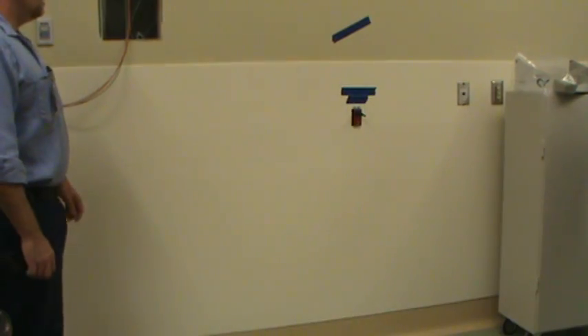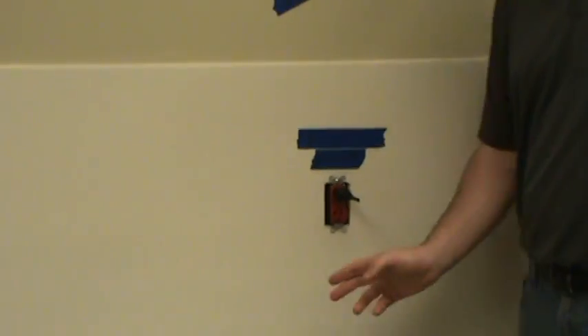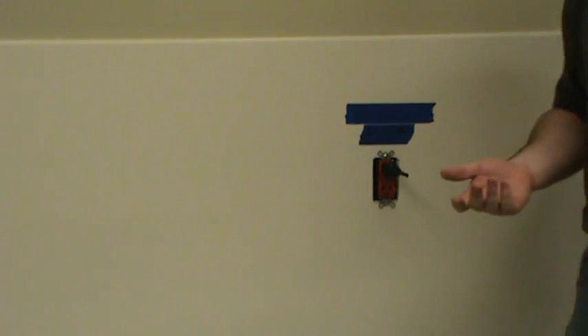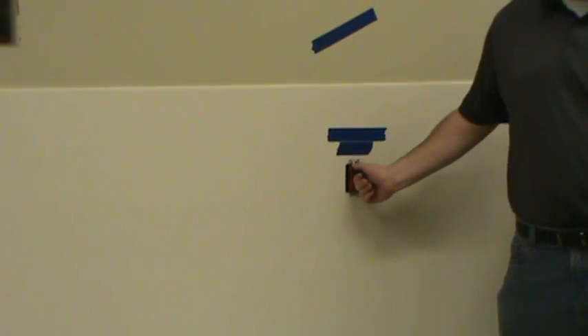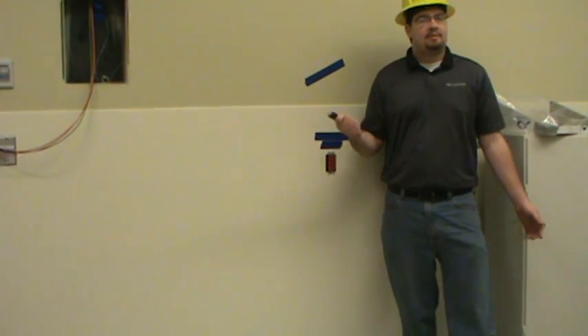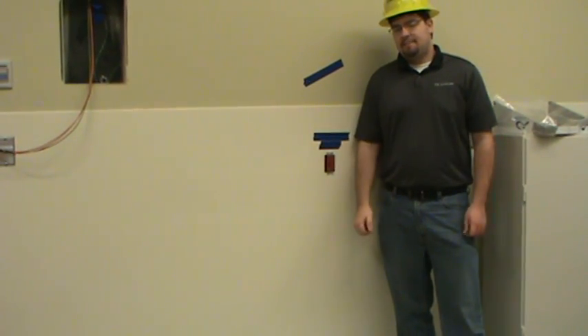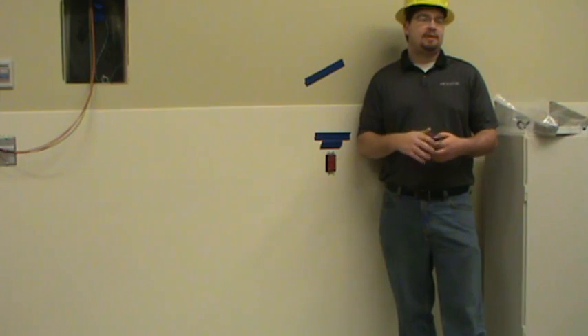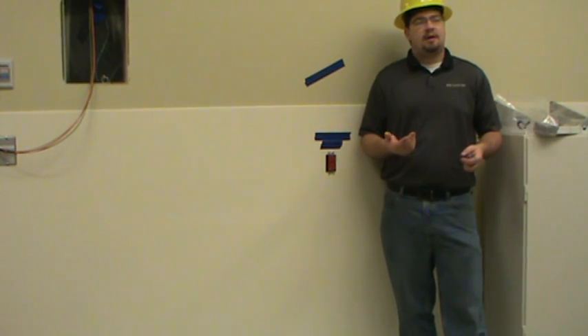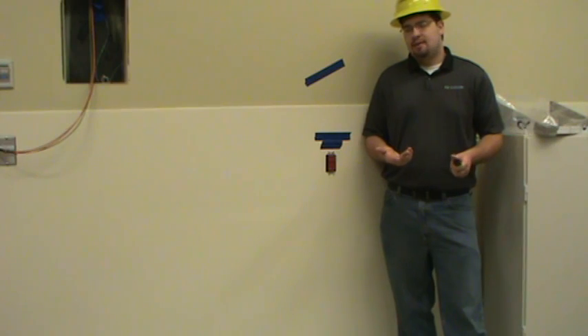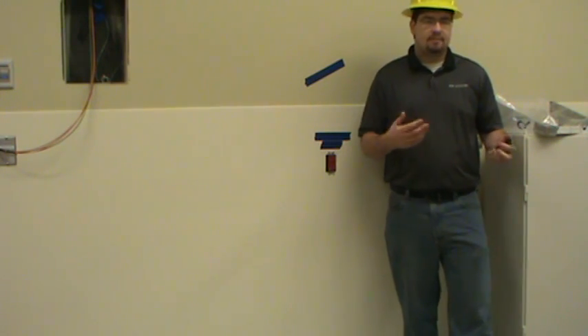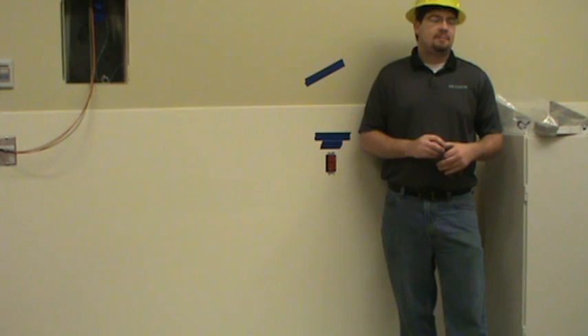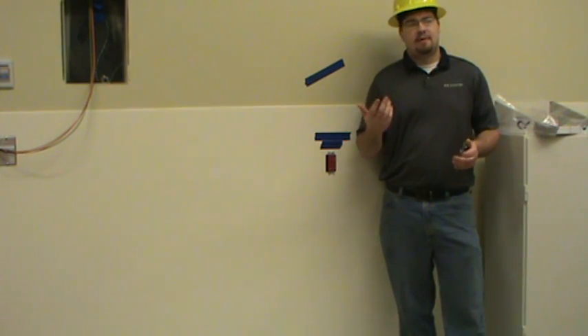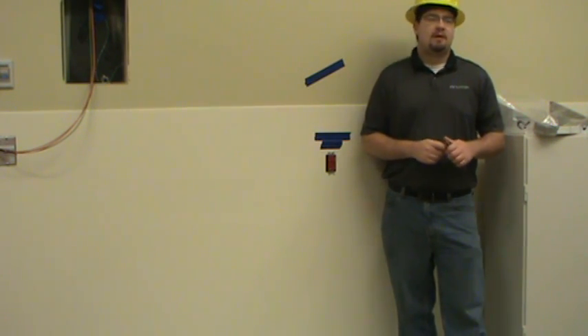So this is just a short from hot to ground. Notice when I plugged it in, we didn't trip a breaker. All we're getting is that alarm. What that means is, usually you can identify it by the first or the last thing you plugged in. You take it out, it's going to go off. Like you were saying before, if you don't know what it is, you can try flipping off individual breakers and isolating it that way. The procedure is if they can't turn off that alarm immediately, to get the patient to a safe state and then move him or her out of the room and then identify the problem more thoroughly.